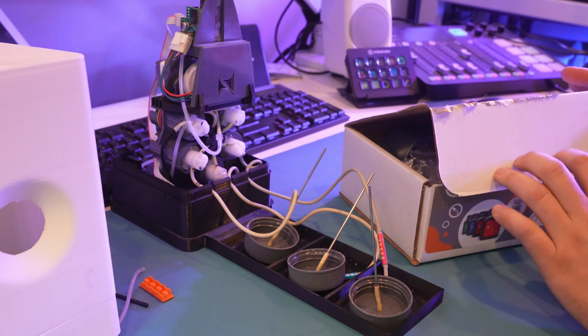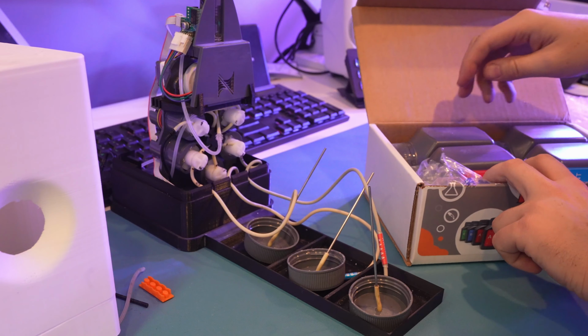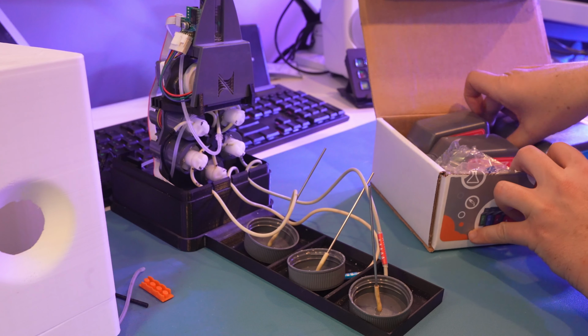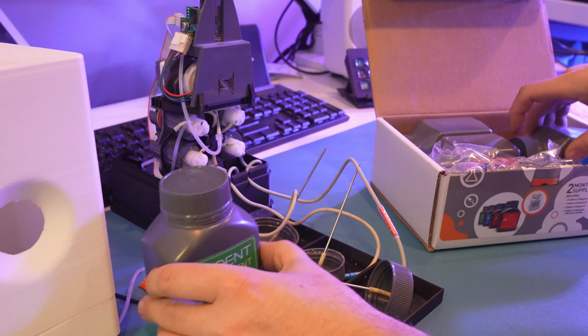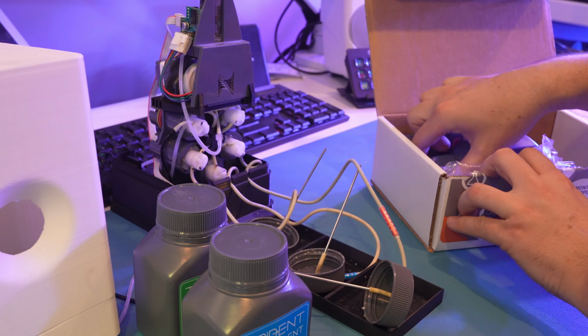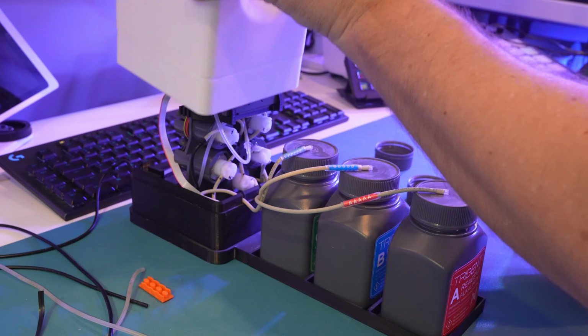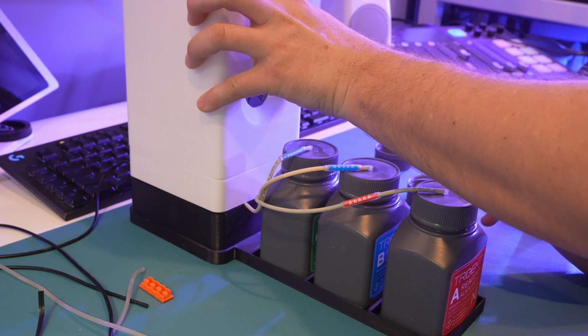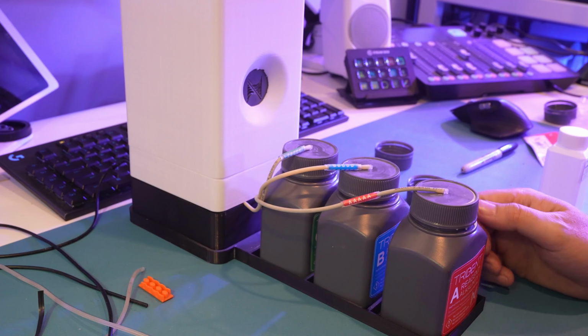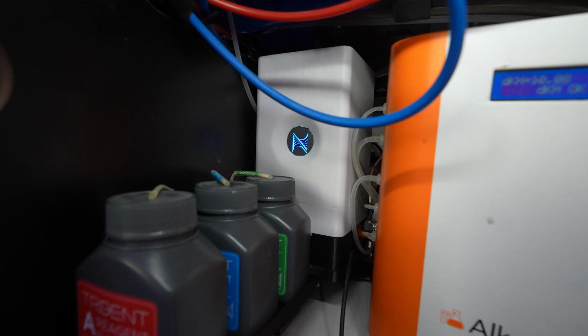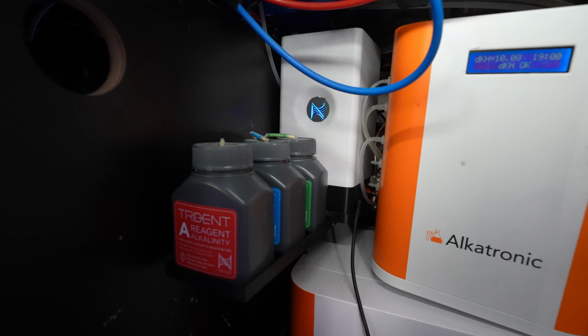Now because we just replaced stuff, it is definitely going to need to be recalibrated, and on that note, we are going to install a fresh pack of reagents alongside it. Alright, should be good to reinstall it and rerun our calibration. Alright, so the little Trident is reinstalled back in her home.